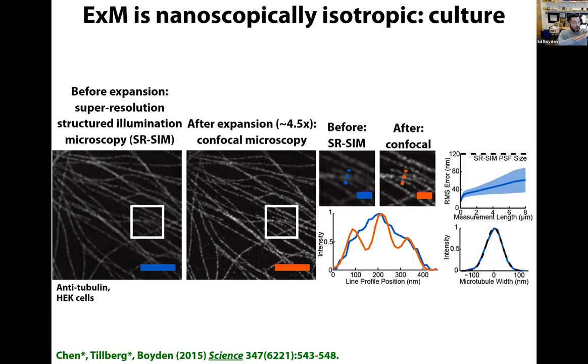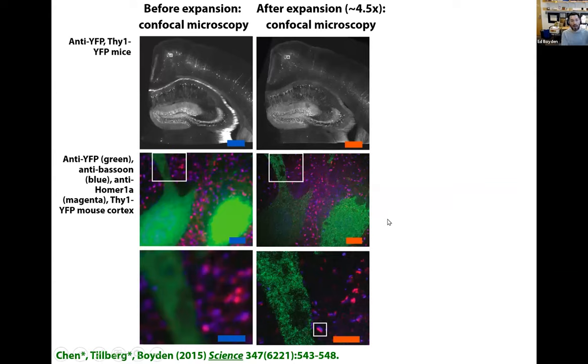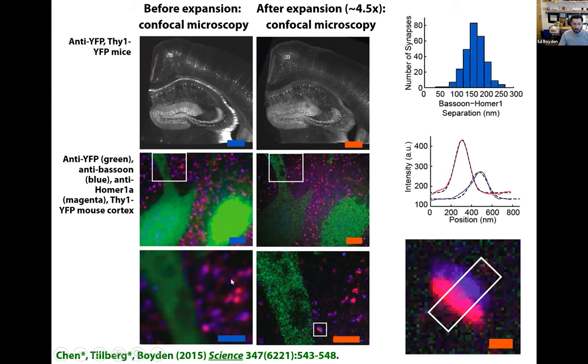We can also measure the resolution. When we expand by four and a half fold, a 300 nanometer resolution lens now has a resolution of 300 divided by four and a half, or about 65 nanometers. Here we have cells in culture with fluorescent antibodies decorating microtubules. We can deconvolve by the known ground truth, since microtubules have been studied for decades with electron microscopy, and we get a resolution around 65 nanometers, which is what we expected.